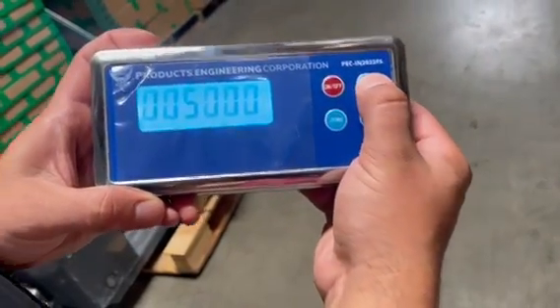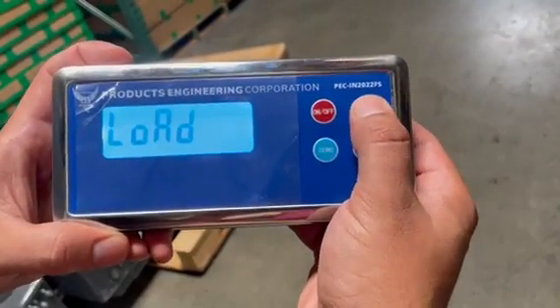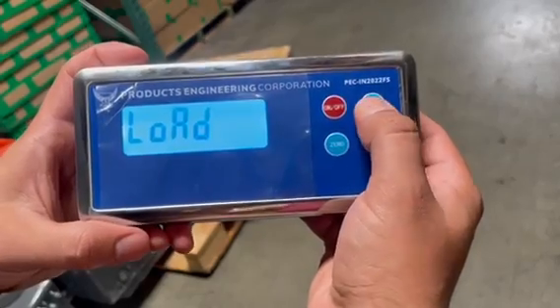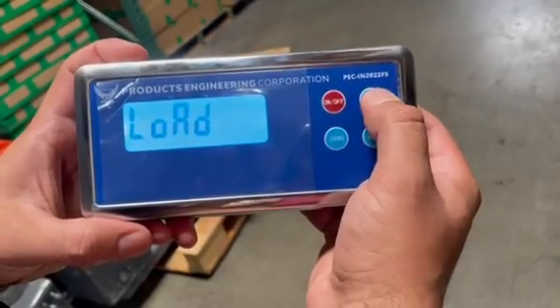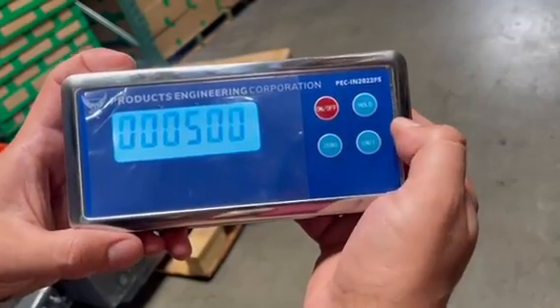Once we have 5,000, we're going to hit hold to set that 5,000 pounds. Now the calibration load is the weight you're going to use to calibrate it — we would use a 500 pound weight. If we hit hold, we have to put 500 pounds here, same as we did on the previous.